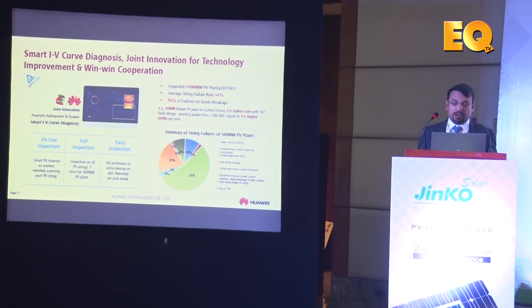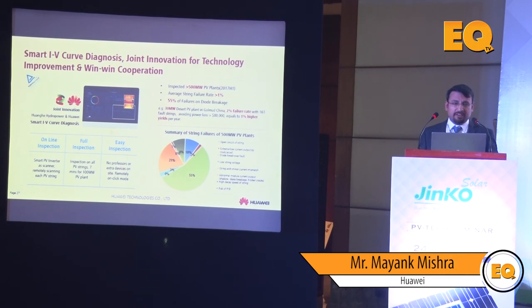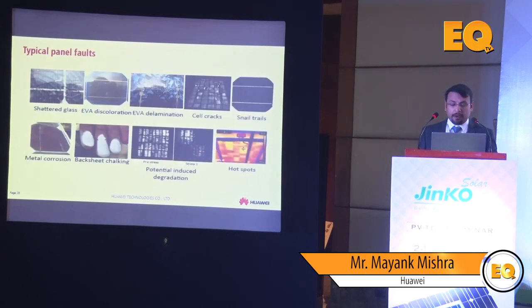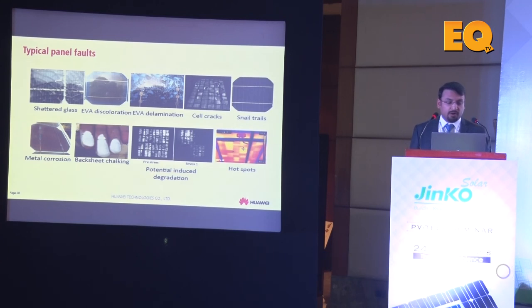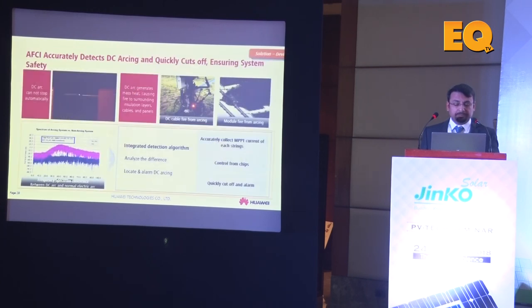You see in the bottom right the summary of string failures for a 500 megawatt PV plant. 55% is the sum of open circuit faults out of the total—55% from open circuit strings with extremely low output. There are 17 different types of faults that can be detected, such as shattered glass, breakage, EVA discoloration, EVA delamination, cell cracks, and snail trails. This helps with better O&M.